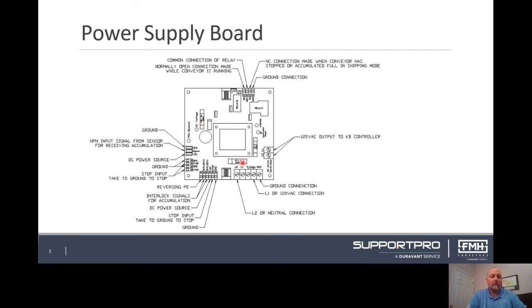The 3 quarter amp fuse controls the transformer or AC side of the power supply. If this fuse is blown, there could be trash on the power supply board causing a dead short or motor voltage feedback to the power supply board.